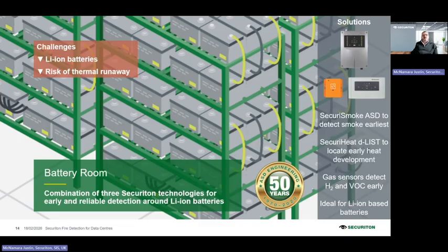Normal detection systems, whether smoke detection or gas detection, are not the best solution if there is a failure of lithium-ion batteries. If a battery fails, whether from mechanical damage, temperature damage, or electrical damage, it will start to emit off-gases, volatile organic compounds, which can be very difficult and tricky to detect.